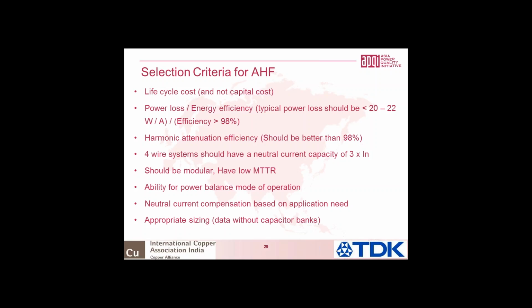Then harmonic attenuation efficiency should be at least 98%. Otherwise, a passive filter would do the job, because passive filters can reach as much as 96% harmonic attenuation efficiency. And if you got a 4-wire system, then the active filter should be capable of correcting unbalance also.